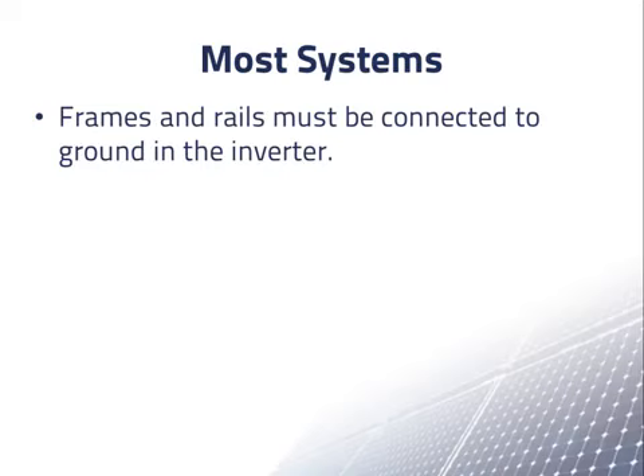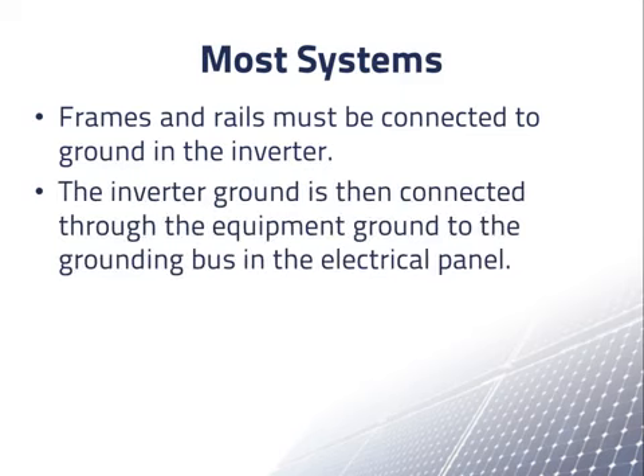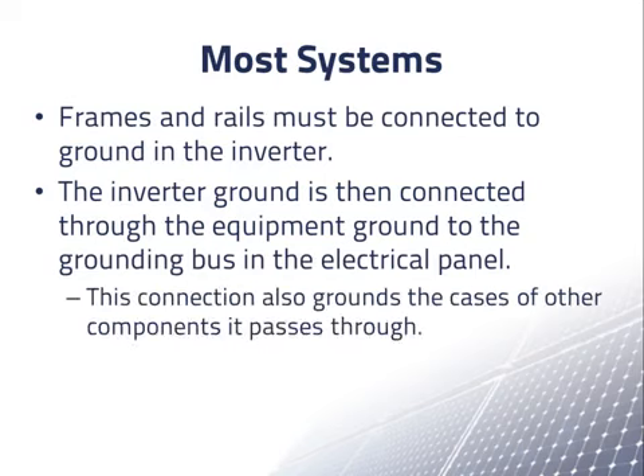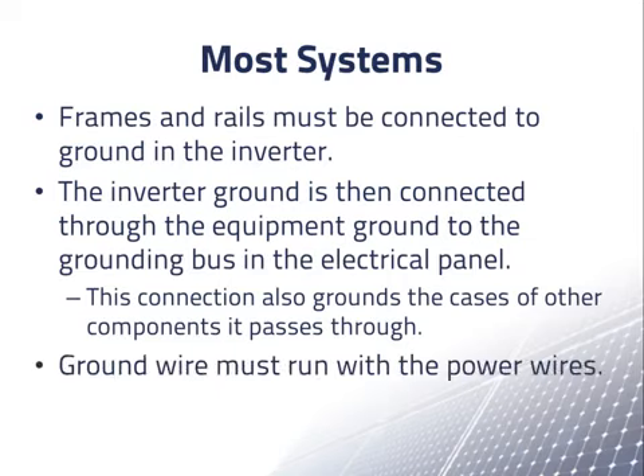In most systems, especially residential and commercial scale systems, we have metallic frames and rails that are required to be connected to ground in the inverter. This means that all of the equipment grounding conductors we saw for modules and rails lead first to the inverter ground. The inverter ground is then connected through the equipment ground to the grounding bus in the electrical panel. This connection also grounds the cases of other components it passes through. Ground wire must run with the power wires.